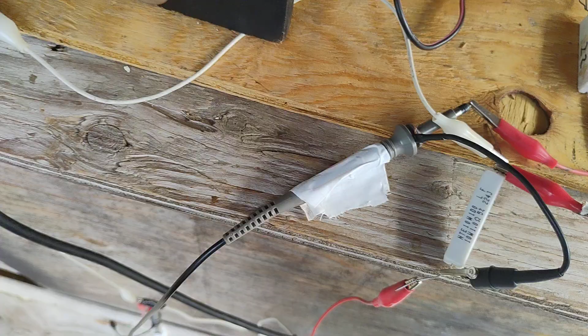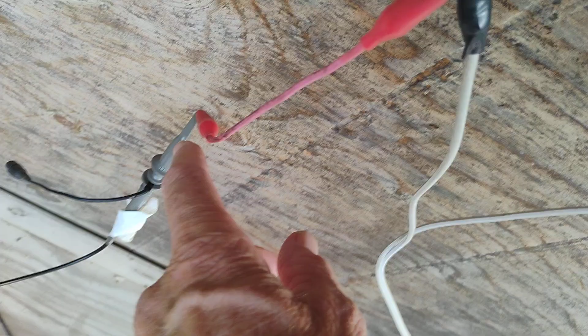So the output then is these two in series, and here's that resistive load to find out what the watts is for the output. And the input is these two white wires. You run one channel picking up the volts over here, with the tip of the scope probe right on one of the AC lines going into the primary, and the other AC line, this white wire, goes in series through a 1 ohm resistor, and the other side of the resistor goes to the other AC line down here. So this is how you hook up the scope.